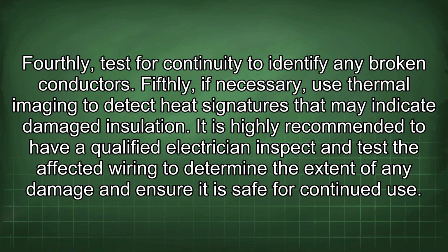Fourthly, test for continuity to identify any broken conductors. Fifthly, if necessary, use thermal imaging to detect heat signatures that may indicate damaged insulation. It is highly recommended to have a qualified electrician inspect and test the affected wiring to determine the extent of any damage and ensure it is safe for continued use.